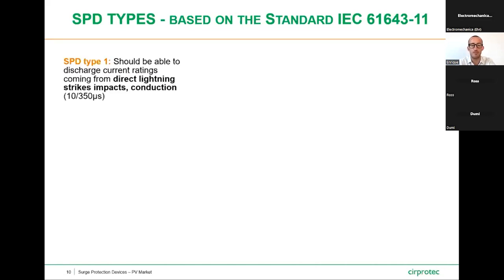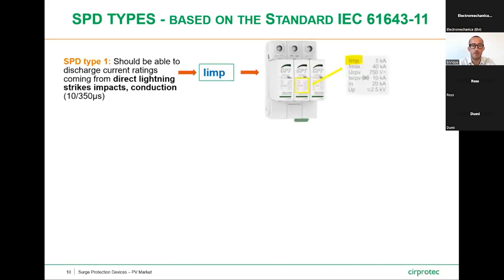Now that we've checked together the parameters shared in the labels certified by each SPD we are working with, we are in a position to share the different types of SPDs based on the standard IEC 61643-11. The first one is the SPD type 1. The SPDs type 1 should be able to discharge current ratings coming from direct lightning strike impacts, which was the scenario shared before, named conduction. The parameter that should be shared by the SPDs type 1 is the Iimp parameter.